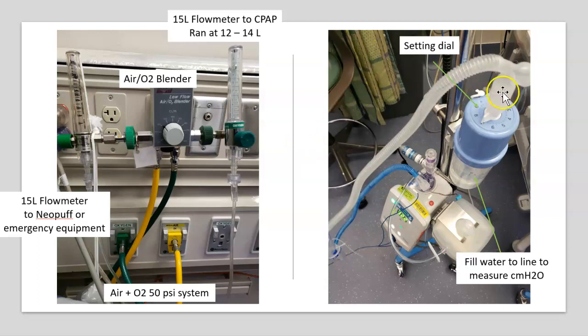From the top, this is the best angle to show you guys. This is our setting dial. This little arrow kind of shows what our setting is. And then we fill it up to this line. I'm literally using centimeters of water pressure to provide CPAP. So we fill up to the line, and this automatically has measured for me our centimeters of water pressure, which is kind of nice. In it, there's also a little straw I'll try to point out, and if I get condensation built up in here, I can withdraw or add water, depending, to make sure I'm getting accurate pressures for my baby. Also, that oscillation from the bubbling is beneficial for little immature alveoli.